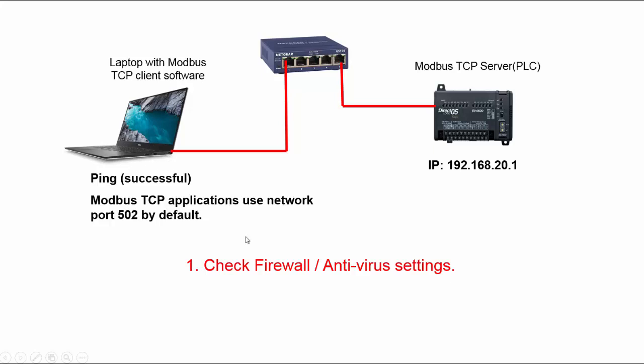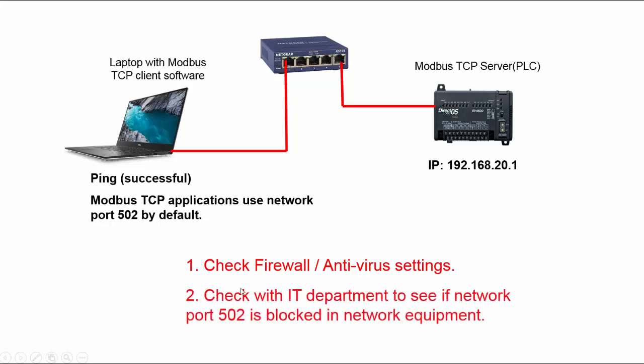The firewall settings especially will automatically block port 502 by default. If port 502 is blocked, a ping would still take place because ping does not use network port 502, but Modbus TCP communication would not. If the firewall settings are fine, I then ask them to check with the IT department to see if network port 502 is blocked in any network equipment.